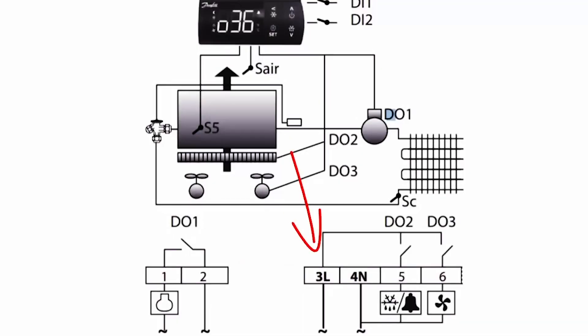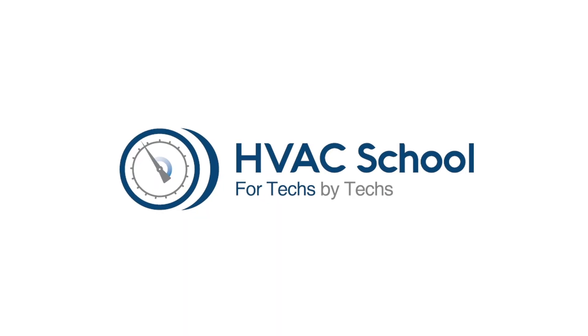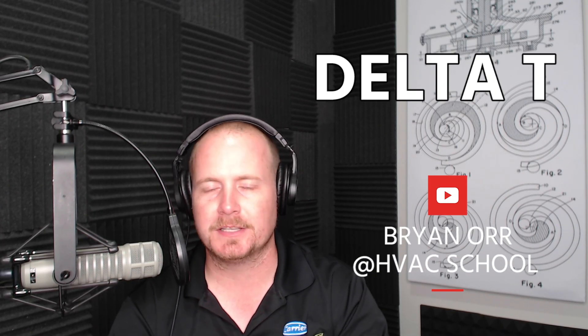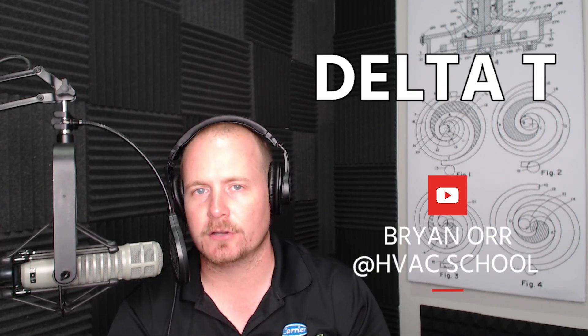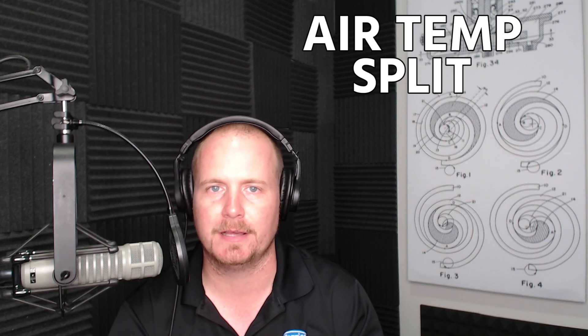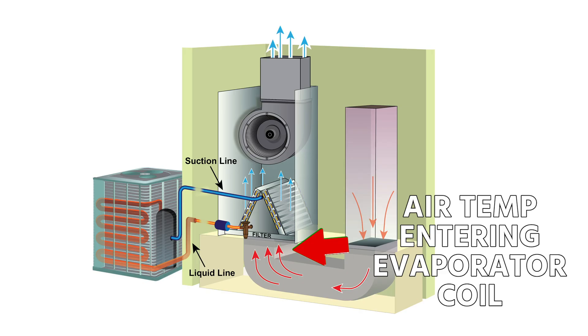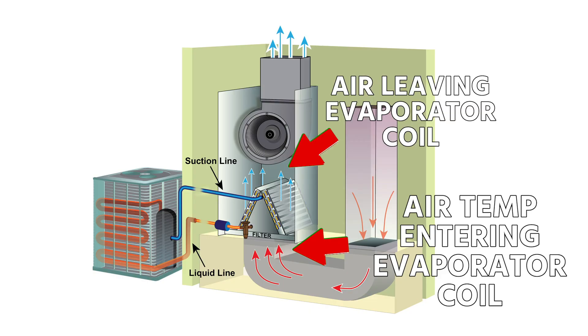This video is all about delta T. Delta T isn't always called delta T — it's often called an air temp split, an air temperature split, or just a temperature split. It's the difference between the air temperature entering the evaporator coil and the air leaving the top of the coil.